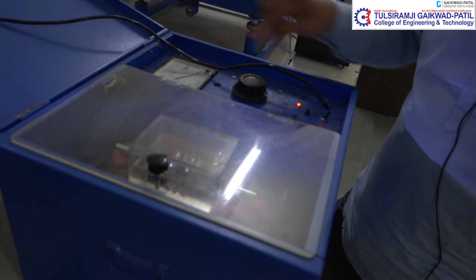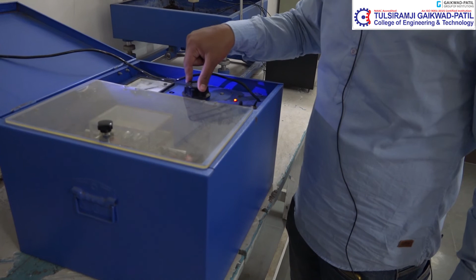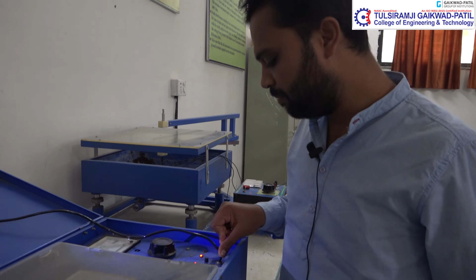Now we have to note down this reading, switch off the HT, and reduce the voltage to 0 kV. Then the 0 start will be on, and we have to switch off the main switch. After doing this, remove the plug from the socket. This way, it is a very easy experiment to check the dielectric strength of a transformer oil or insulating oil. This setup we have done.